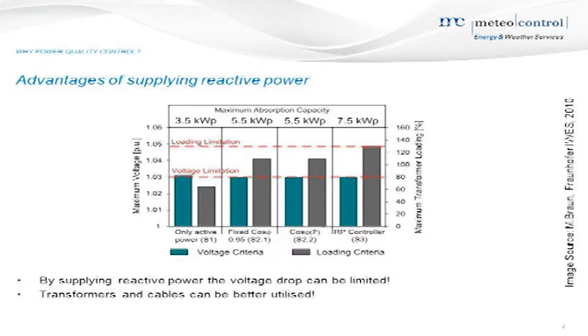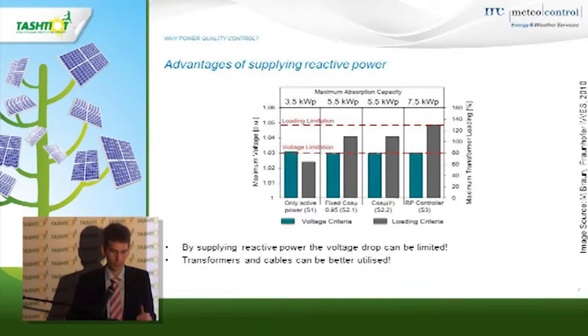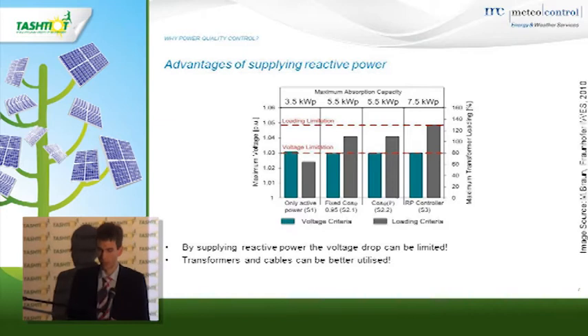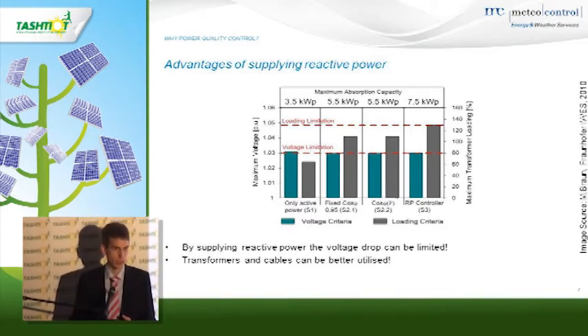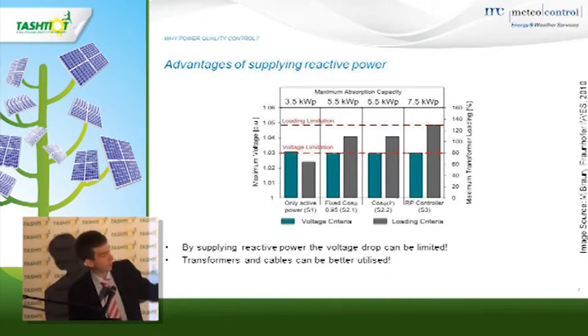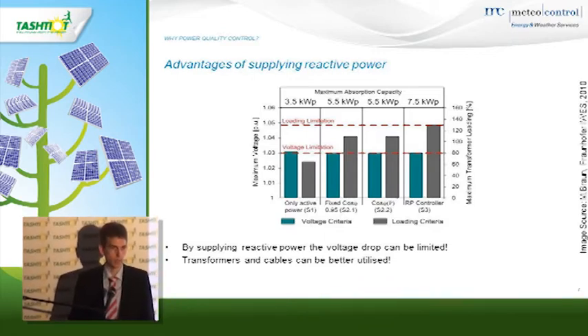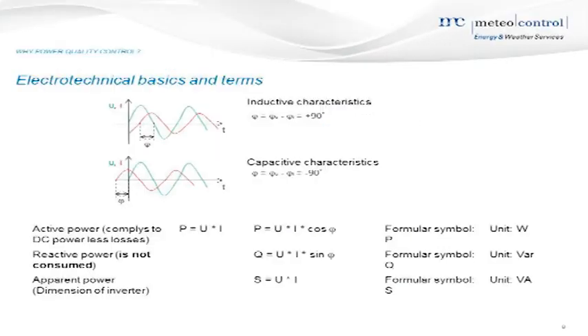There you can see the advantages by supplying reactive power control. The most important one is to limit the voltage drop, so you can utilize your transformer and cables better, or the utility, the grid operator, can utilize it better than on the left side if you just insert active power. So this is a very technical slide because I think we are very short in time. I don't explain this one.